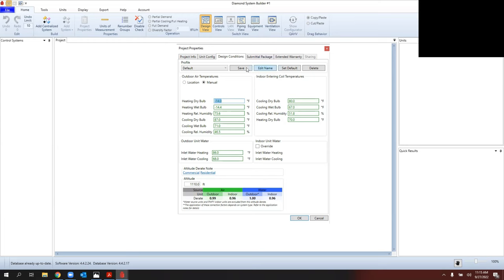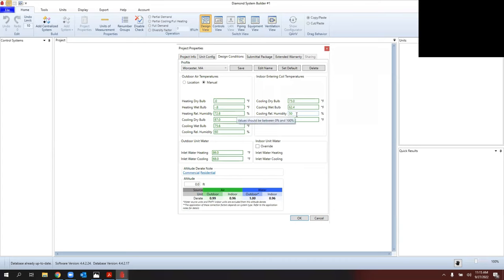Once you have the area you always work in, save it and set it as default so every time you open DSB it opens with that default. For example, I live closest to Worcester, Massachusetts — selecting Worcester auto-fills design temperatures. Inside temperatures are set by code: cooling dry bulb is 75°F with 50% relative humidity as required by the IECC and IRC. For heating dry bulb, the code allows plus or minus two degrees from 70°F, so between 68°F and 72°F.